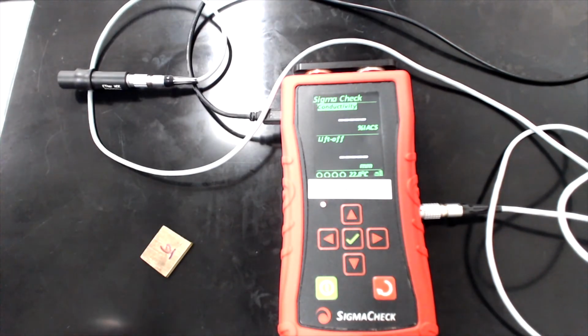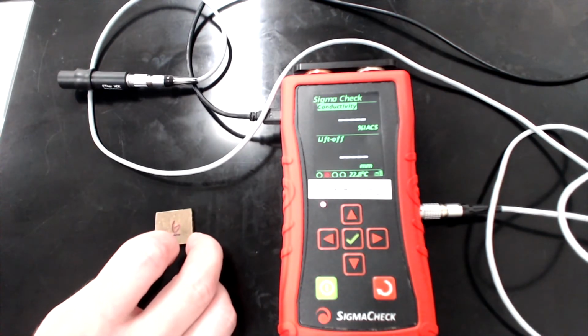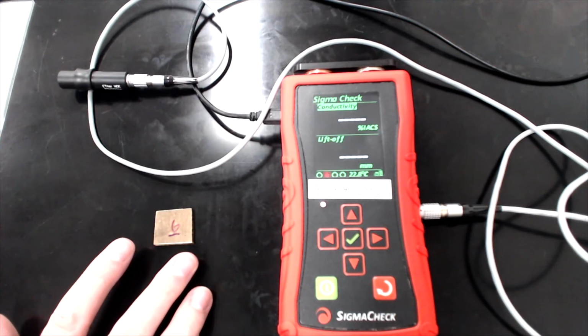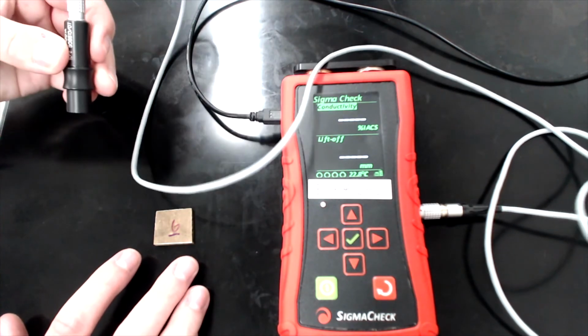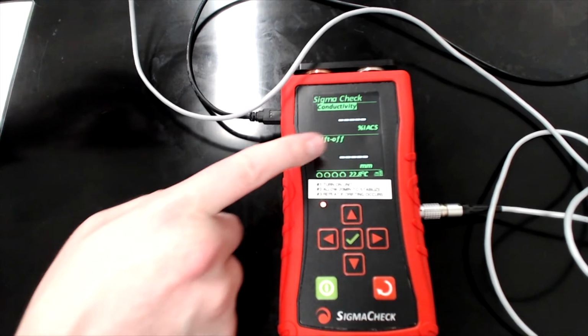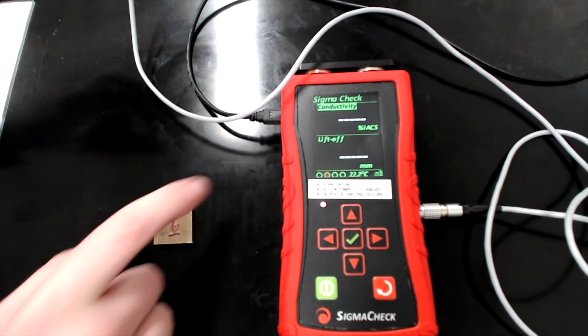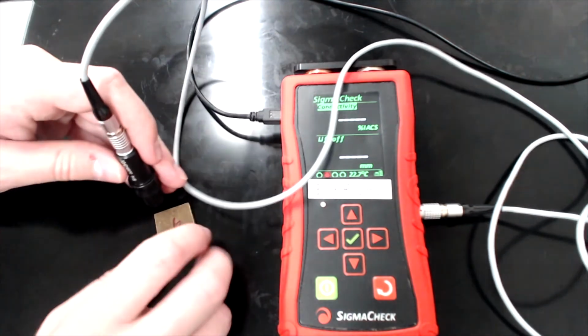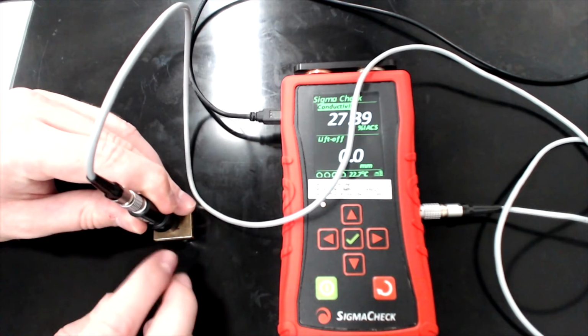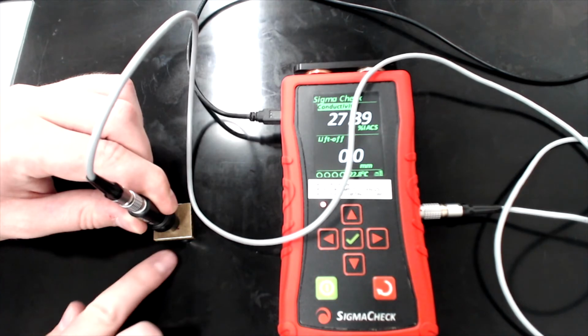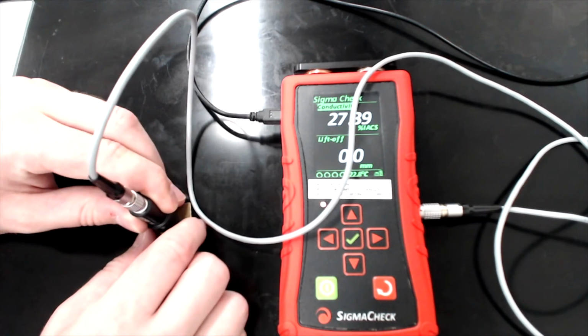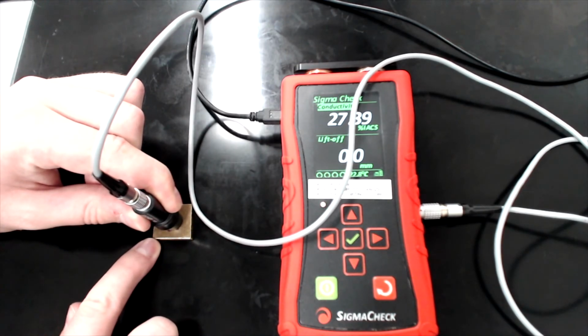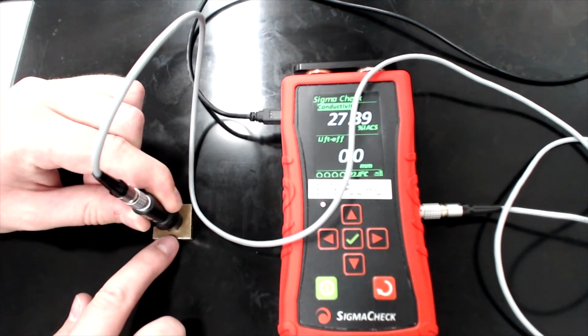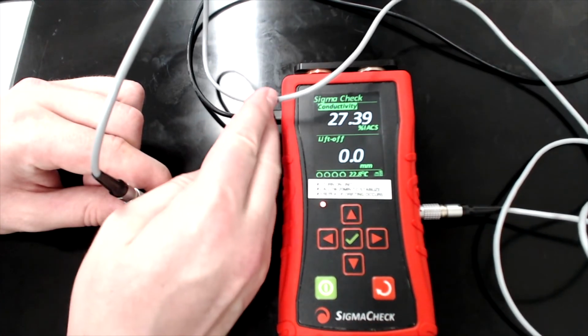All right, so we have units, we have a quick overview of all of the quantities that this machine can give you, and we're ready to test the conductivity of our test sample here. And again, this is just from last semester. It's not important for your data. But I'm going to take the probe. I've got the conductivity and the units specified here, and I'm going to leave it on liftoff, but we can go back and forth. So I'm going to basically press it flat on the test piece and make sure that I'm not moving it around. You'll also notice that the test piece is big enough to accommodate the probe. So you want to make sure that it's larger than the probe. And so we've cut these pieces specifically such that they're bigger than this probe. And so now it's stabilized, it hasn't moved.